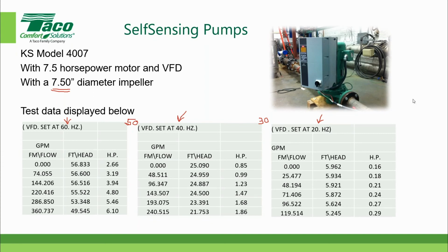And again, as I mentioned a moment ago, there is a relationship between the flow in gallons per minute and the power. As the flow increases, the power increases, and that holds true for each of the individual speeds. So once I have collected this data very accurately, I now have a relationship between speed, power, flow, and head. Since the variable frequency drive, the self-sensing drive itself, is an electronic device, it can easily keep track of its own speed and its own power consumption, and it looks up the data that we provided after taking careful measurements in the laboratory. We call it lookup data.